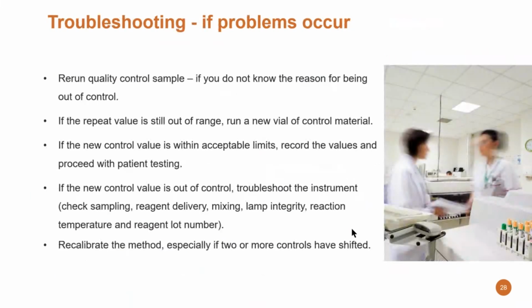Troubleshooting if problems occur. There's always the recommendation to rerun the quality control sample. This, for me, is if you don't know the reason and you're not sure if you have used the proper control material. But if you rerun just the same quality control material, you might get exactly the same value. So if you repeat the value and it's still out of the range, you may run a new vial of quality control material. If the new control value is within the acceptable limits, so within the 3SD range, record the values and proceed with testing of the patient samples. If the new control value is out of control, outside of 3SD, troubleshoot the instrument, checking the sample, reagent delivery, mixing, lamp integrity, reaction temperature, and last but not least, whether there is a change of the reagent lot number.